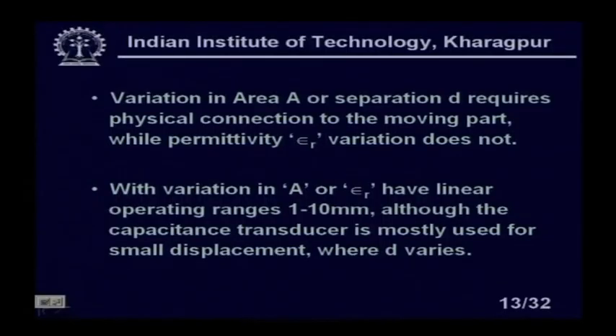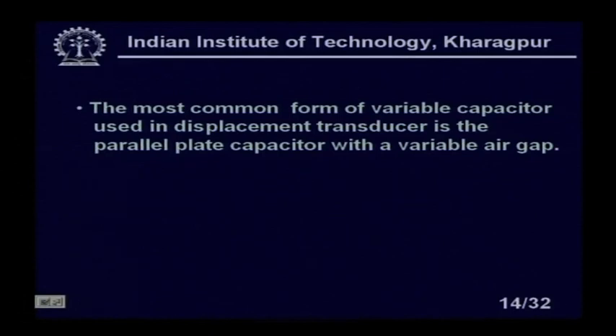With variation in A or εᵣ, there is a linear operating range, usually 1 to 10 mm. Capacitance is mostly used for small displacement where D varies. For larger displacement, we use other sensors like potentiometers. Usually, the capacitance sensor is used for smaller displacement measurements. The most common form of variable capacitor used in displacement transducers is a parallel plate capacitor with a variable air gap.